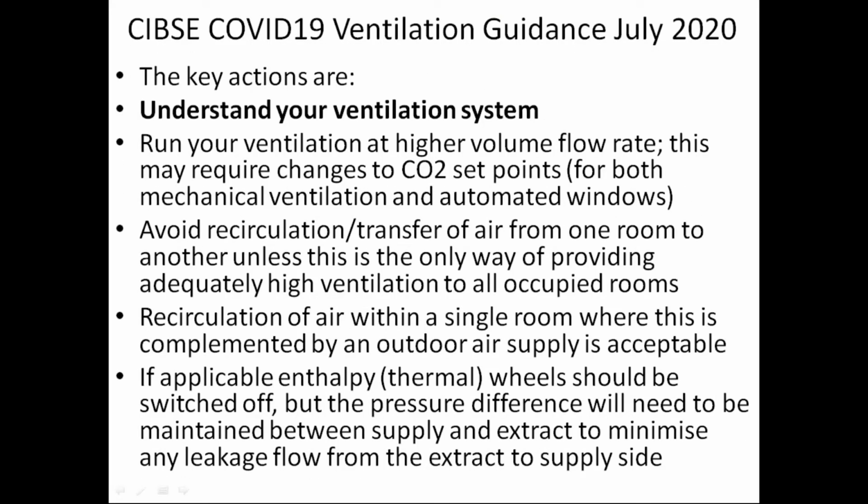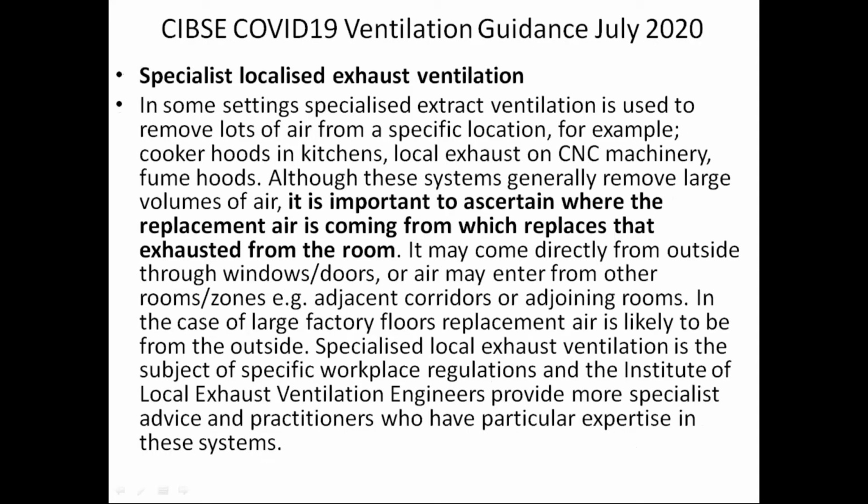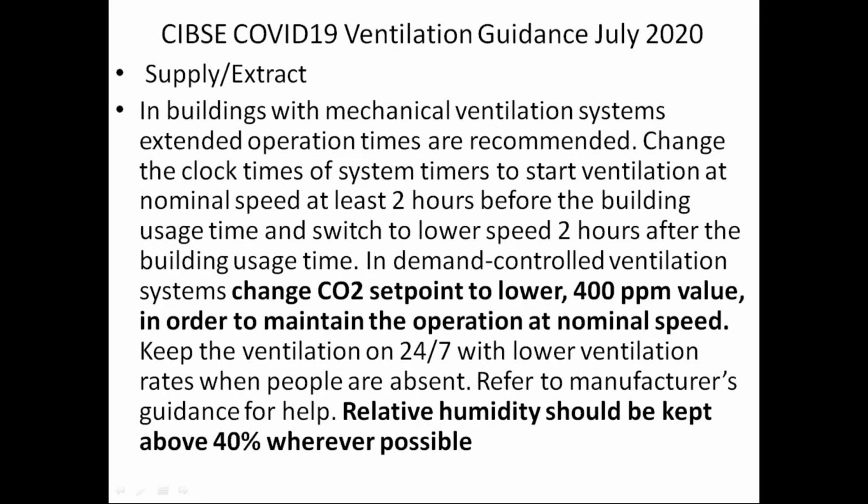So in any risk assessment, you need to understand your ventilation system, and you need to be careful with any energy saving measures put into the system, like CO2 set points. You need to keep the system running. Local exhaust systems are effective in catching the source locally, but you need to be careful and understand where the air is coming from. As I explained earlier, CO2 set points need to be lower to keep the system on. CIBSE also acknowledged relative humidity.